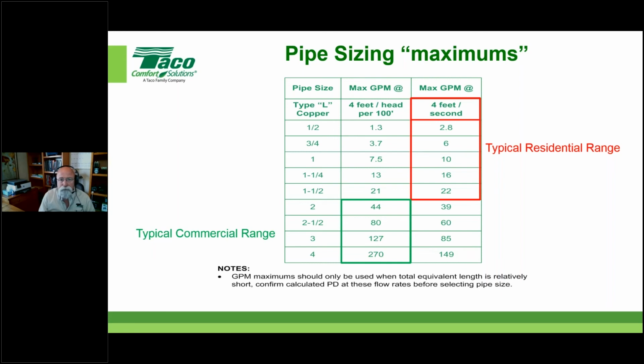Right. And oversizing the system pipe, that oversizing the header is actually a good thing. It simply aids in hydraulic isolation. It does on that close near boiler header, right, for multiple zoning. Absolutely, that's your near boiler piping secondary header, and it wants to be generously sized or copiously sized, however you want to say it.